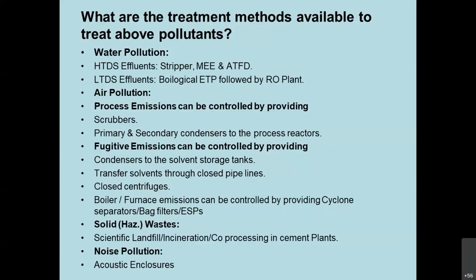Next, boiler or furnace emission can be controlled by providing different types of air pollution control equipment. If it is a small capacity boiler, then a cyclone separator is enough. If the boiler capacity is more than 4 TPH or 5 TPH (tons per hour), then we should go for bag filters, pulse jet bag filters, and ESPs, electrostatic precipitators.